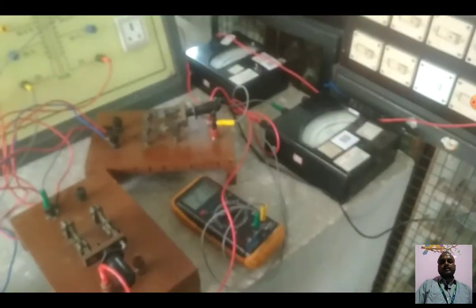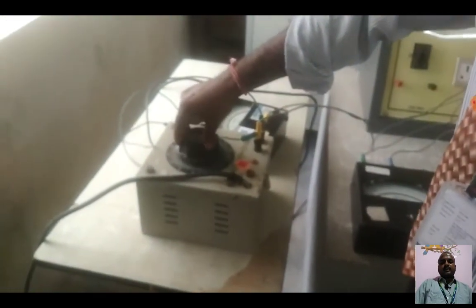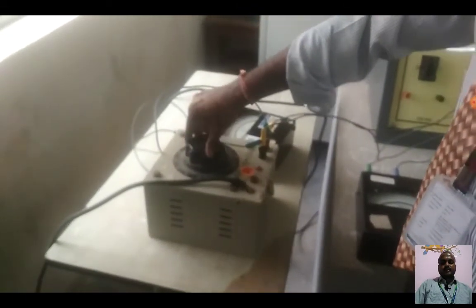After noting down the readings, I have taken three readings. After the readings, release the load on the transformers, that is, switch off the load, open the DPST switch, which you can call the load switch, and open the SPST switch. Reduce the auto transformer to the 0 position. Then switch off the main supply.